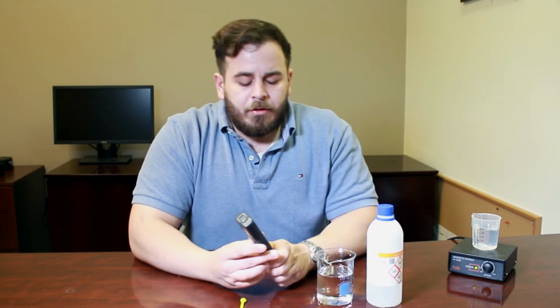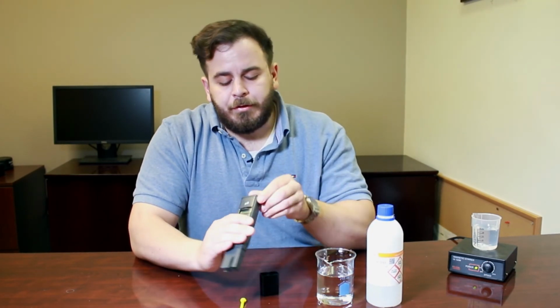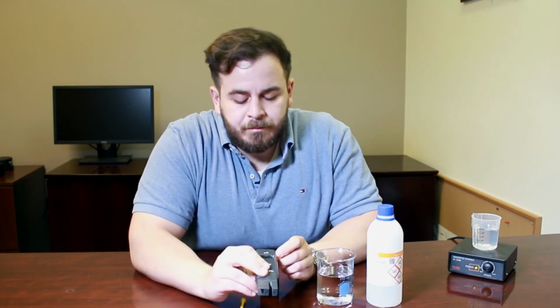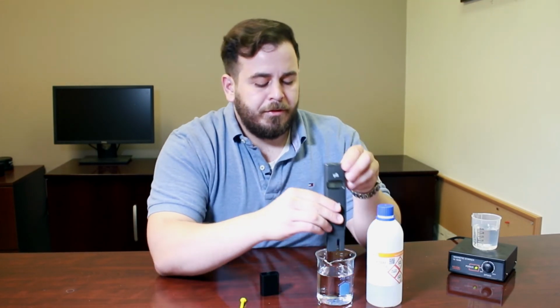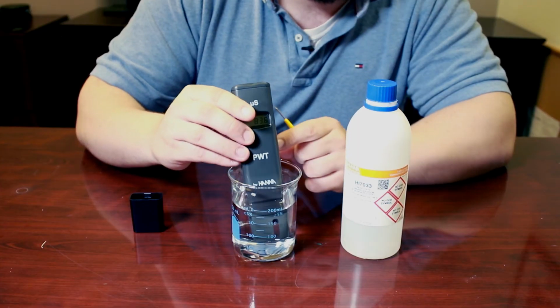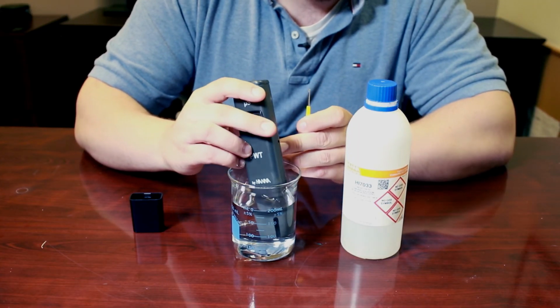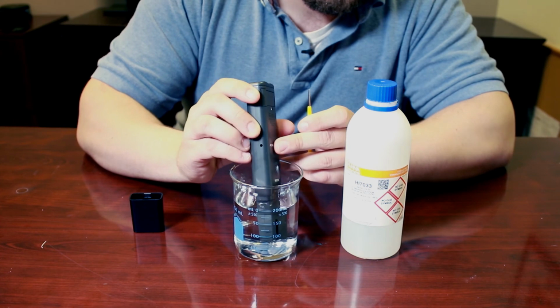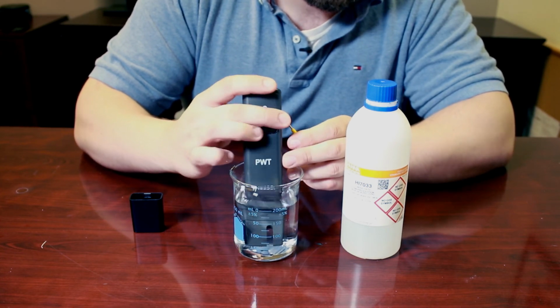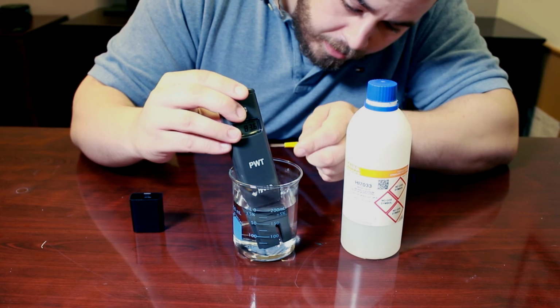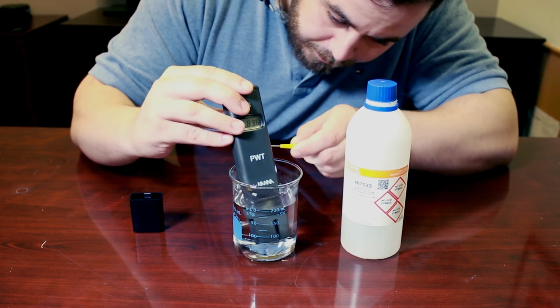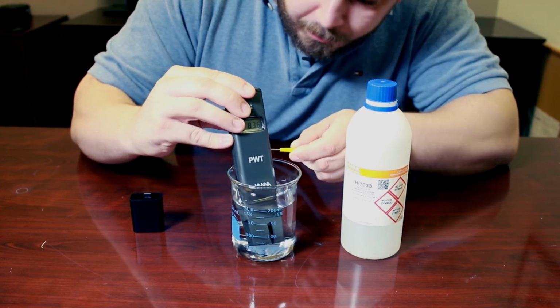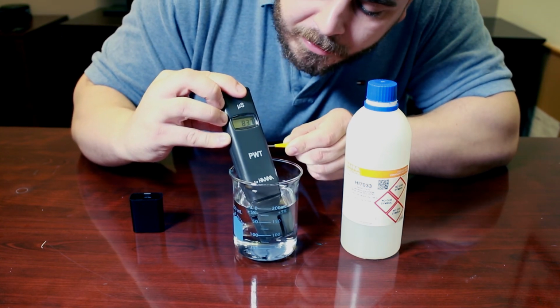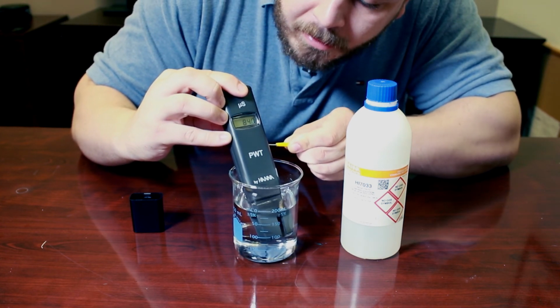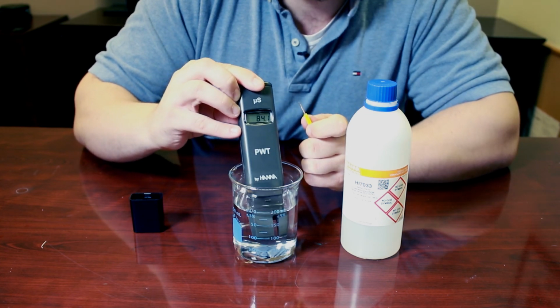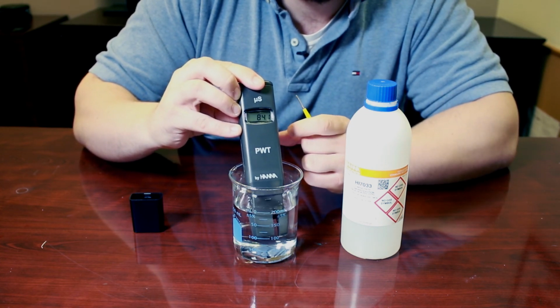So if we were going to calibrate the meter, the first thing we do is turn it on with the top switch up here. Then we submerge the meter inside the calibration standard and use our little calibration screwdriver. You can see on the back of the meter, it says calibration right there with a little arrow pointing to this hole. Inside that hole, you're going to see a little screw. When you insert this screwdriver, you're just going to gently turn it until the meter reads the value of 84. Once it reads that value of 84, you know your meter is calibrated.